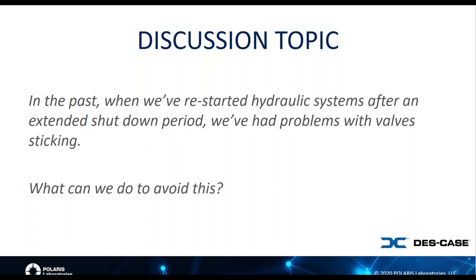And interestingly, there are some pretty good studies that have shown that the force you need to move a hydraulic valve in a fluid that has been aged for a prolonged period of time is significantly higher, 2 to 3 times higher than the force you would need to move that valve in a new fluid that has not been oxidized. So it's not uncommon to see operational issues, slowdowns, slowing cycle times, valves that stick, even valves that fail to actuate when a machine has been shut down for a while.